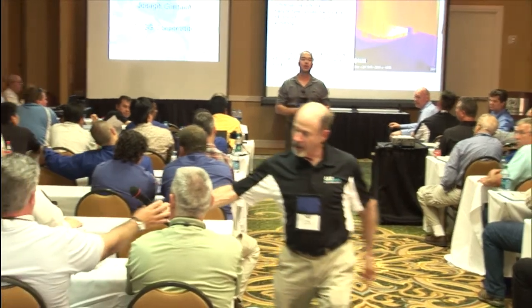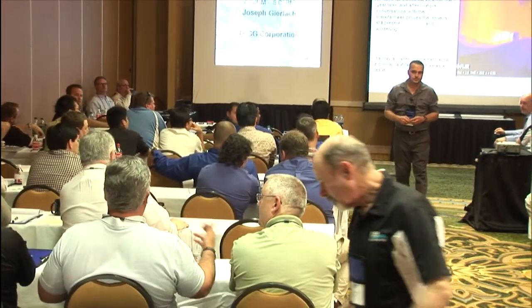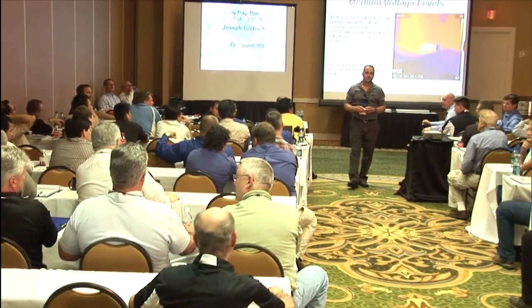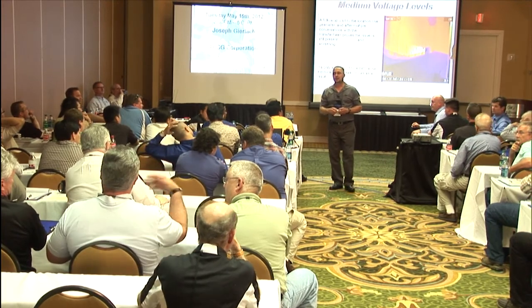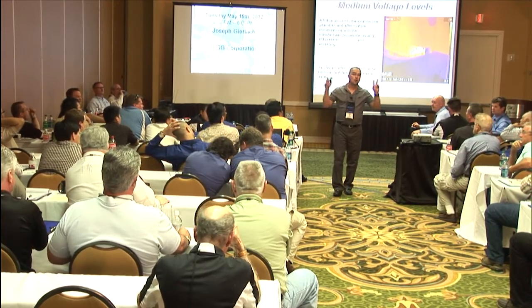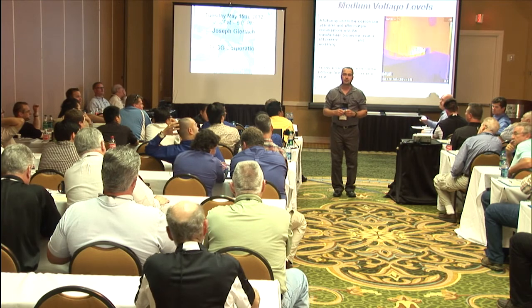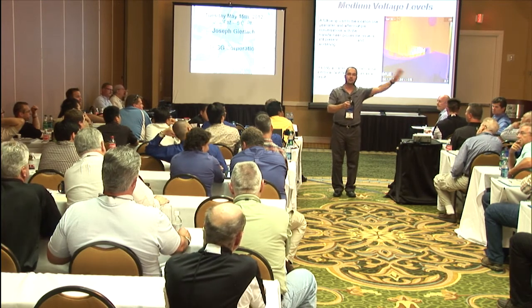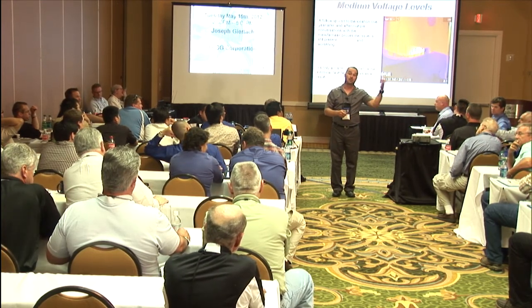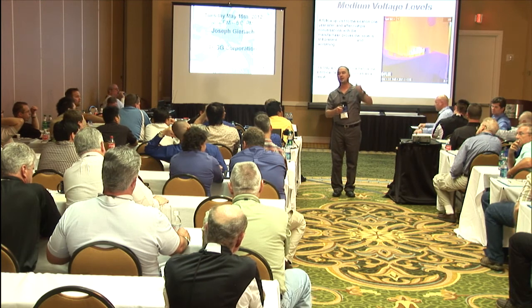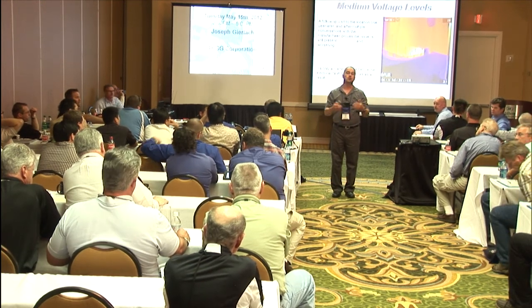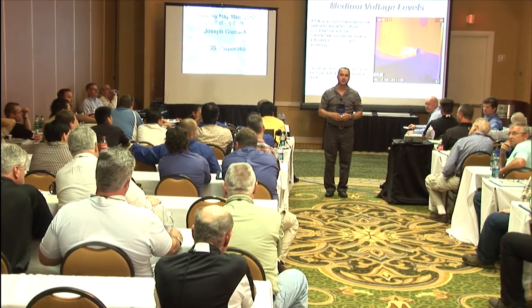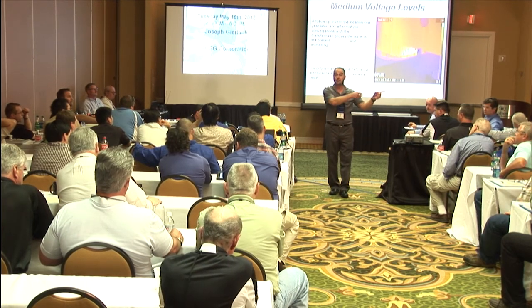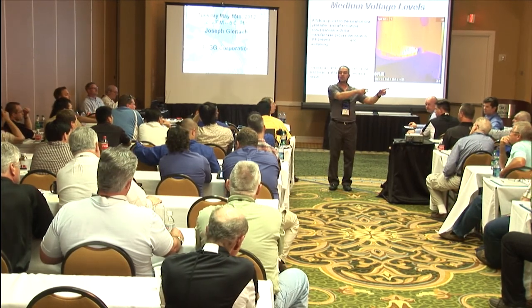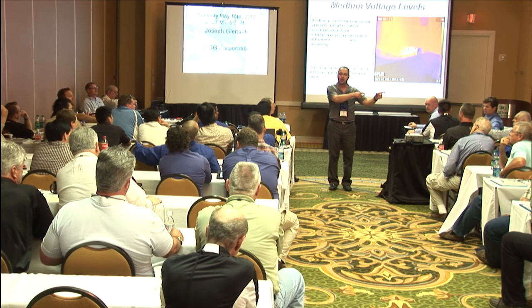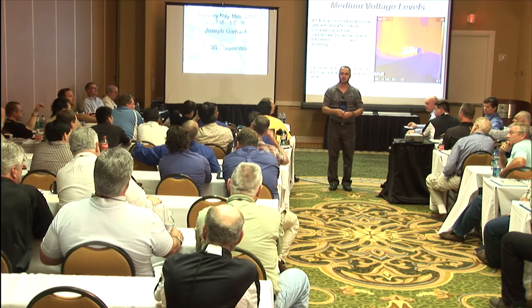What do you mean, mess the harmonics up? They end up getting dirty power going down through there, and it ends up messing things up — I mean, I know if it's a hospital. Yeah, it could cause some noise on the line, but related to harmonics, that's actually a product of the loads within the facility that produce them and send them back toward the transformer. So you may get some electrical noise on the line, which is bad for the sensitive loads, but it's actually those sensitive loads that produce the harmonics that return on the system.